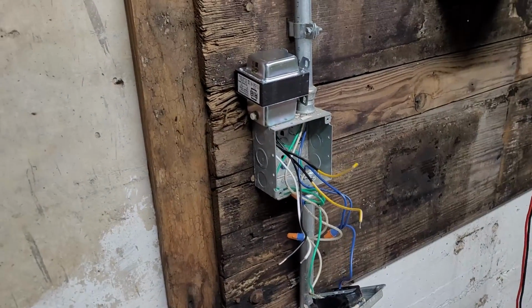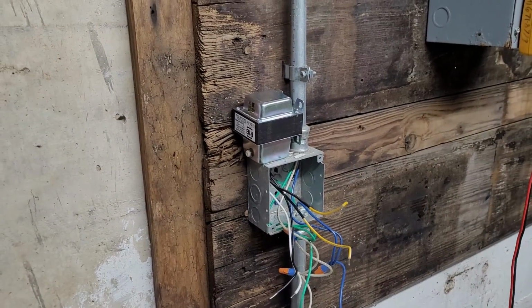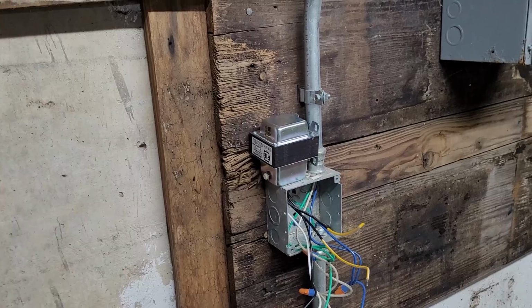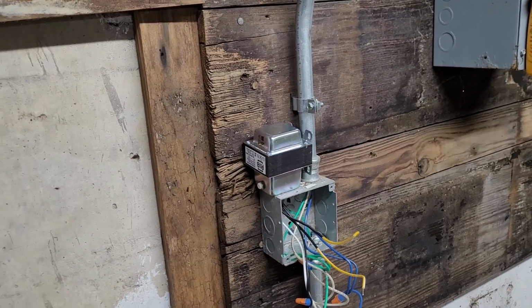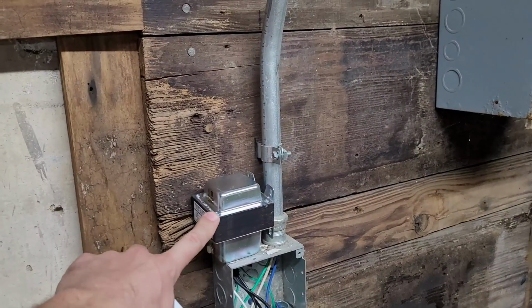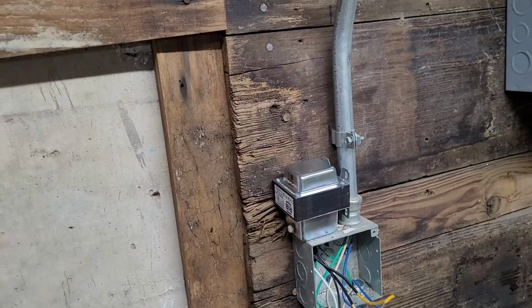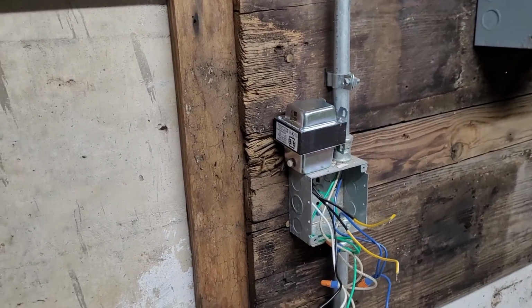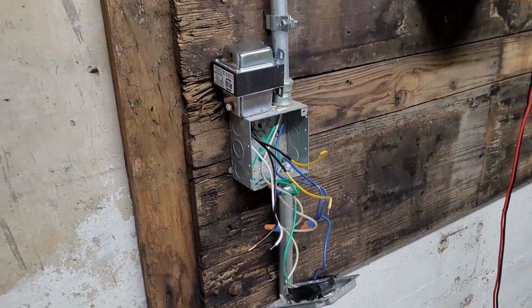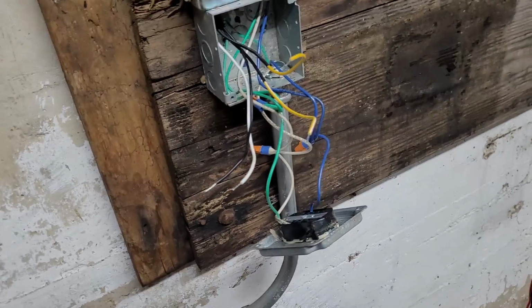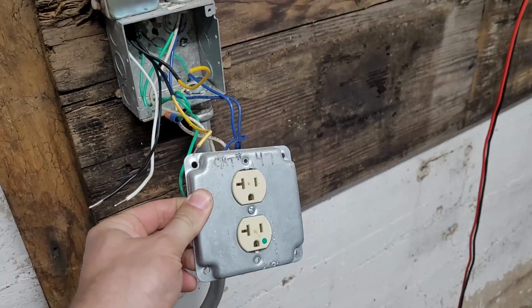So a good place to add a step-down transformer is, now, it has to be run off of a constant source of power. You don't want something that's switched. Like you wouldn't want to add a transformer to a light ballast, right? Because the lights are going to get turned off. So you need to make sure that your power source is constant. A good place to find a constant power source is at a receptacle.